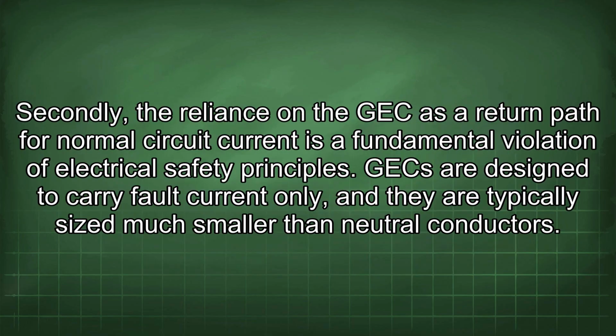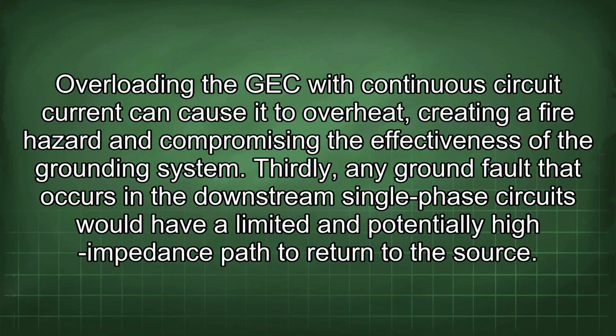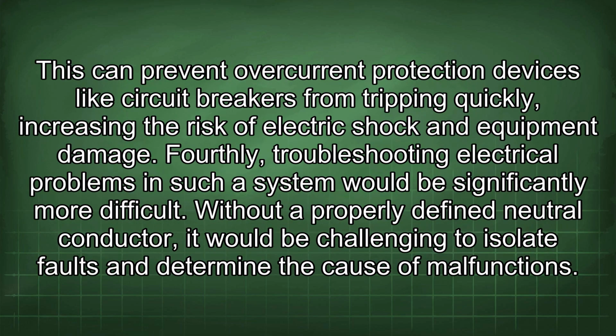electronic equipment. Secondly, the reliance on the GEC as a return path for normal circuit current is a fundamental violation of electrical safety principles. GECs are designed to carry fault current only, and they are typically sized much smaller than neutral conductors. Overloading the GEC with continuous circuit current can cause it to overheat, creating a fire hazard and compromising the effectiveness of the grounding system. Thirdly, any ground fault that occurs in the downstream single-phase circuits would have a limited and potentially high impedance path to return to the source.